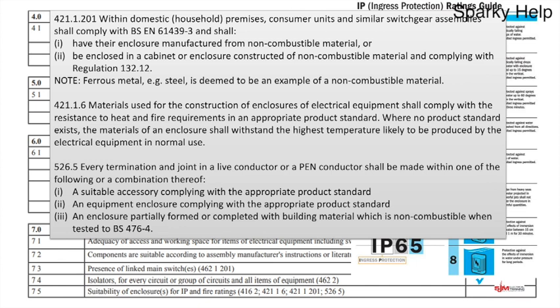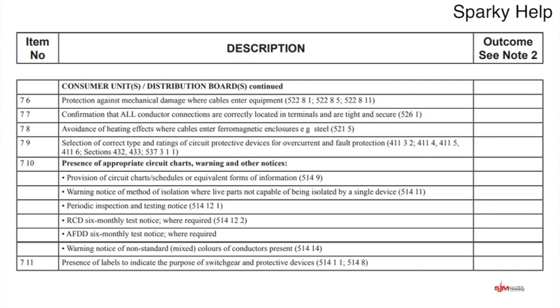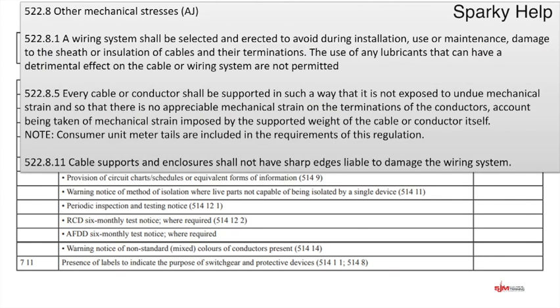As we've said, distribution boards are metal and shouldn't be able to burn down effectively. So there's the regulations that go with that particular one there. Hopefully a tick. Let's go over the page. The consumer unit's distribution board. Protection against mechanical damage where cables enter equipment. So does exactly what it says on the tin. Mechanical damage is physically something hitting your cables. So if cables are entering your distribution board, are they protected for the environment which they were in?